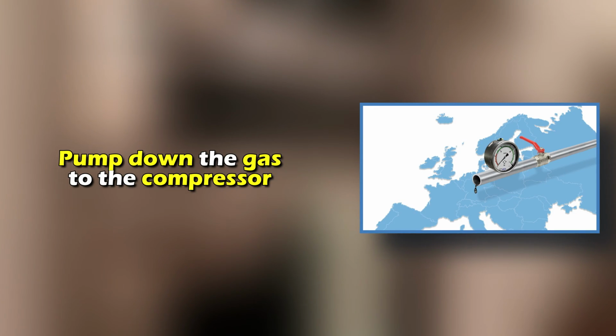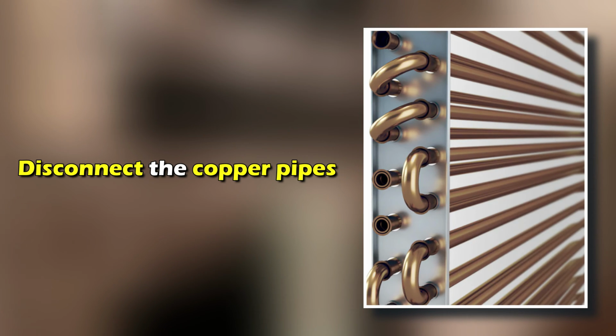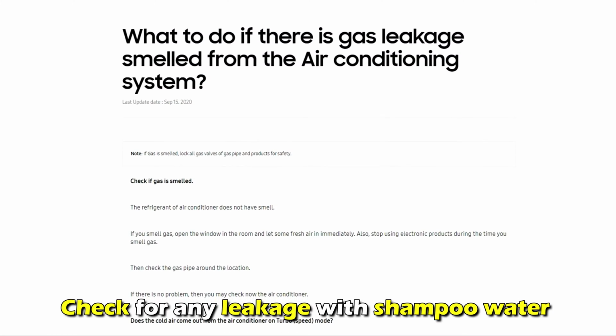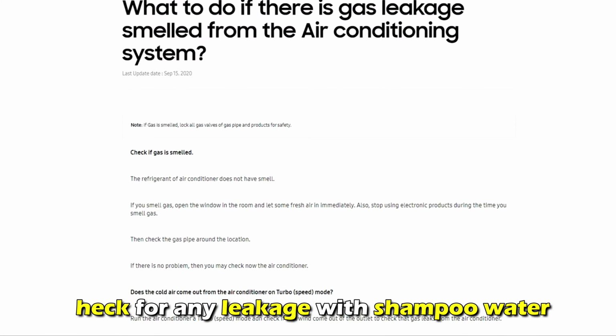Fix the gas leaks. To seal a gas leak, use this procedure: switch off the unit and pump down the gas to the compressor, then disconnect the copper pipes and check for any leakage with shampoo water.